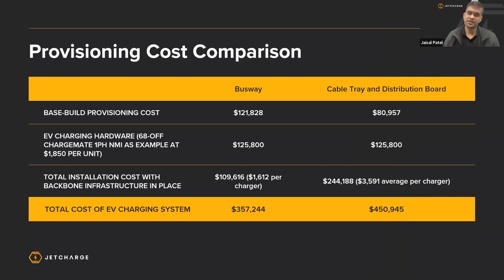So how does the cost stack up? We've done a high level costing for both options, with the base-build provisioning costs being approximately 121,000 for the busway solution and 80,000 for the cable tray and distribution board method. Using a 7 kilowatt, 32 amp single phase charger for each resident, that typically costs about $1,000 to $3,000 per unit. We've used a $1,850 per unit charger as our example unit here. Costs about $125,000 to give every resident in the car park a charger.